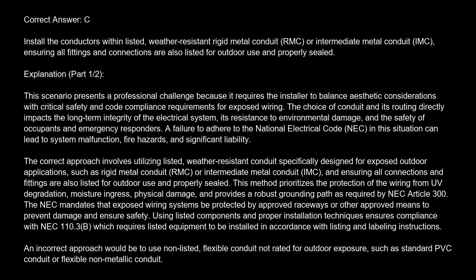A failure to adhere to the National Electrical Code, NEC, in this situation can lead to system malfunction, fire hazards, and significant liability. The correct approach involves utilizing listed, weather-resistant conduits specifically designed for exposed outdoor applications, such as rigid metal conduit RMC or intermediate metal conduit IMC, and ensuring all connections and fittings are also listed for outdoor use and properly sealed. This method prioritizes the protection of the wiring from UV degradation, moisture ingress, physical damage, and provides a robust grounding path as required by NEC Article 300. The NEC mandates that exposed wiring systems be protected by approved raceways or other approved means to prevent damage and ensure safety. Using listed components and proper installation techniques ensures compliance with NEC 110.3(B), which requires listed equipment to be installed in accordance with listing and labeling instructions.